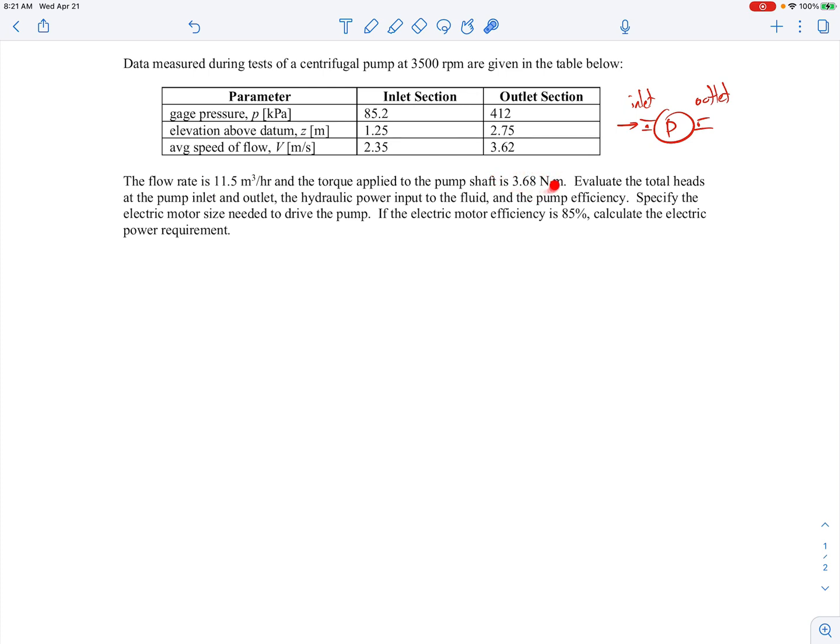The torque applied to the pump shaft is also given. We're asked to find the total heads at the pump inlet and outlet, the hydraulic power input to the fluid, and the pump efficiency. We're also asked to specify the electric motor size needed to drive the pump if the motor efficiency is 85%.